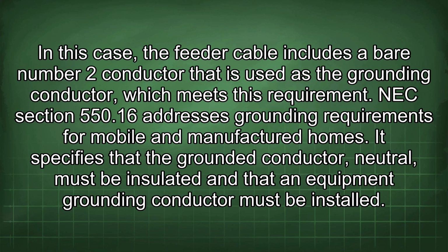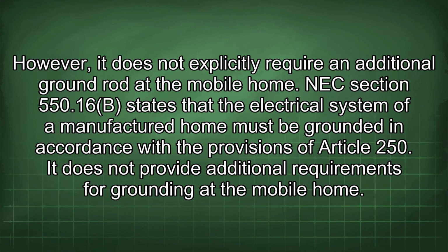meets this requirement. NEC Section 550.16 addresses grounding requirements for mobile and manufactured homes. It specifies that the grounded conductor, neutral, must be insulated and that an equipment grounding conductor must be installed. However, it does not explicitly require an additional ground rod at the mobile home. NEC Section 550.16(B) states that the electrical system of a manufactured home must be grounded in accordance with the provisions of Article 250. It does not provide additional requirements for grounding at the mobile home.